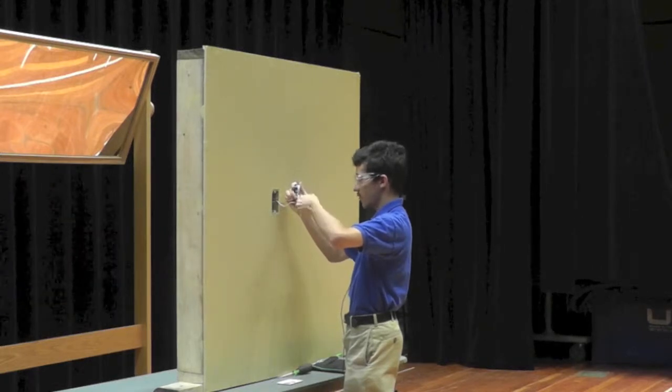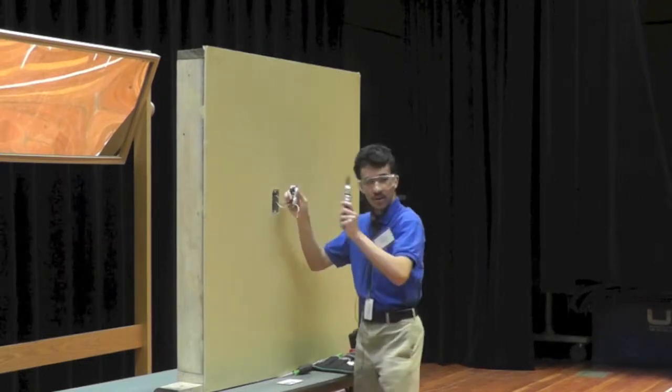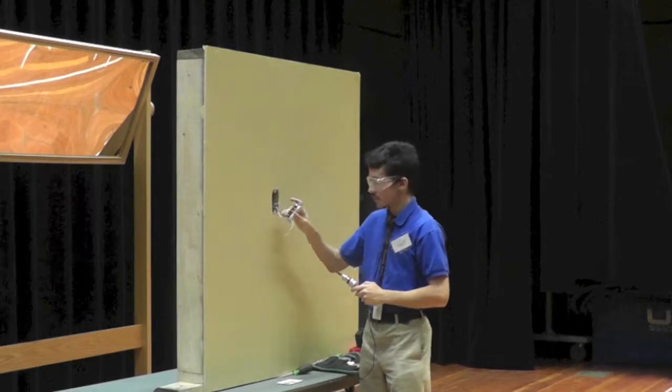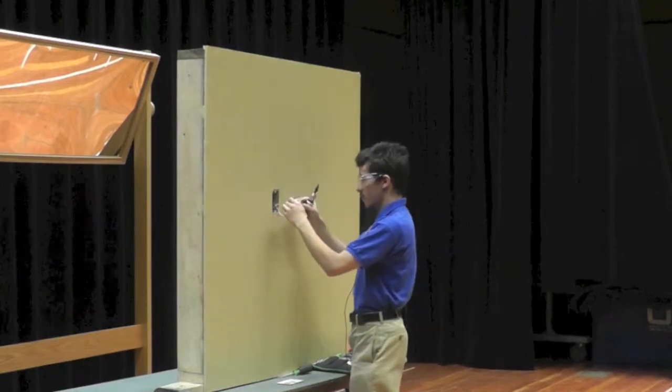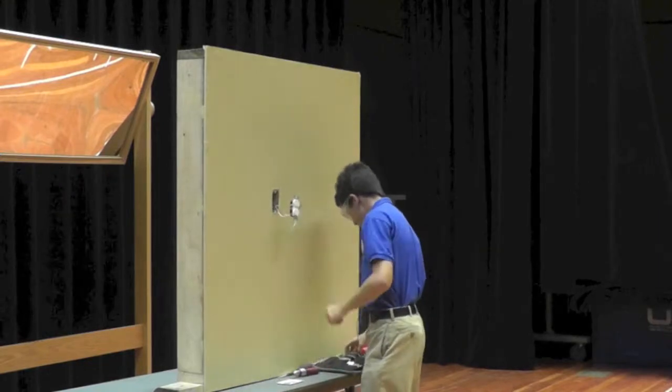And we will turn this until we hear a click. And this click means the screw has been sufficiently tightened to 7 inch-pounds and we will continue to do this until all conductors are reinstalled.